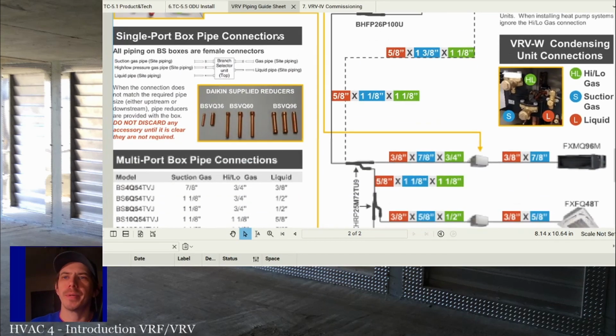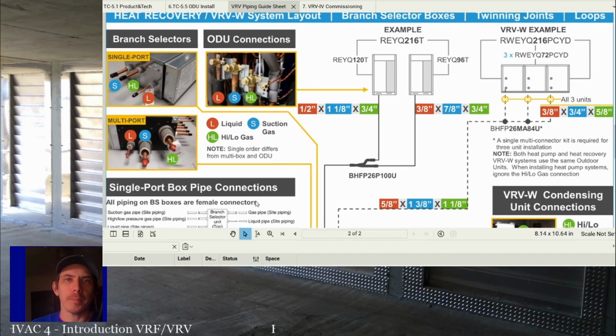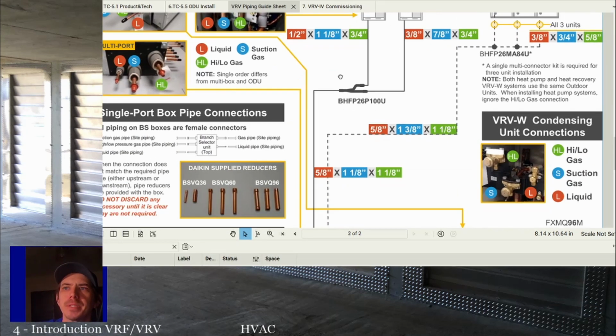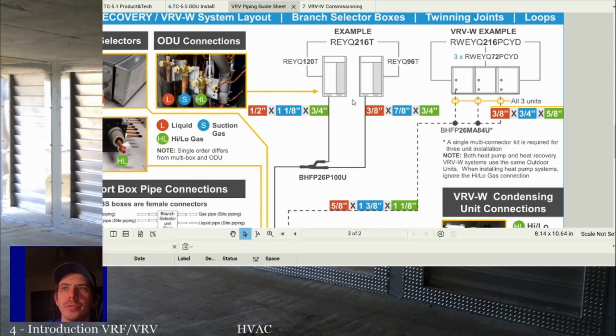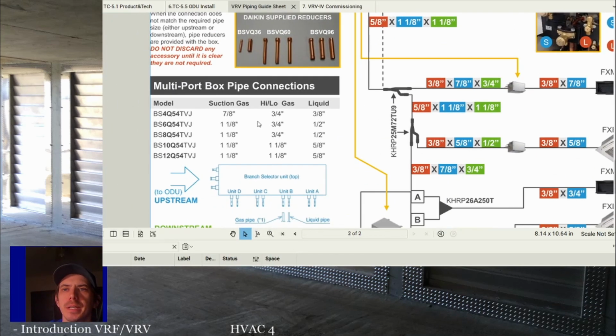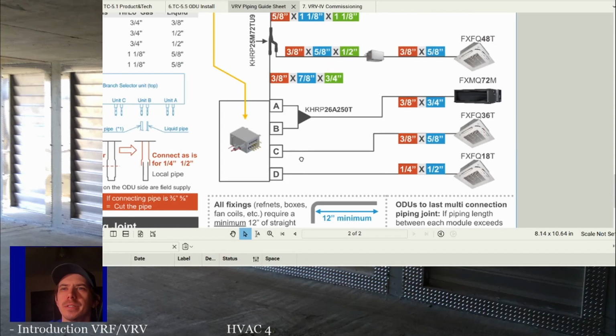This is a heat recovery piping sheet. And this is one of the complicated things about VRF systems. And it's not that complicated, but it's important to make sure you understand it if you're working on a VRF system, or even if you're trying to diagnose problems, looking for installation errors that could cause issues. So, again, talking heat recovery, we're going to have 3 pipes. And these 3 pipes have to go from the outdoor units. They will tie together at the outdoor units with these special fittings. And this is where the individual manufacturers get a little different.